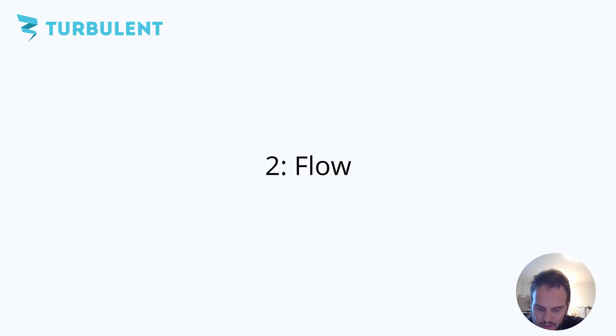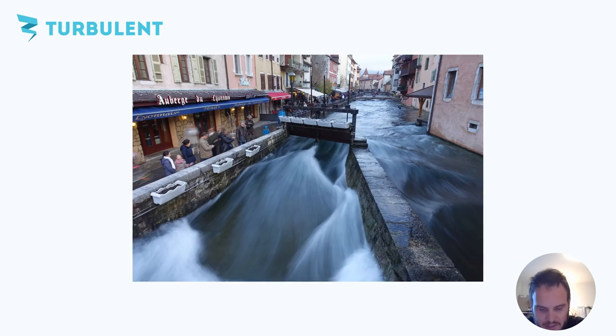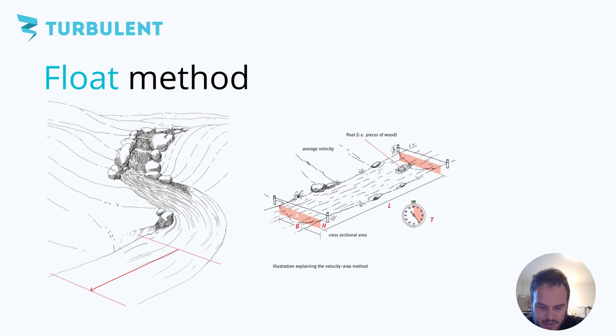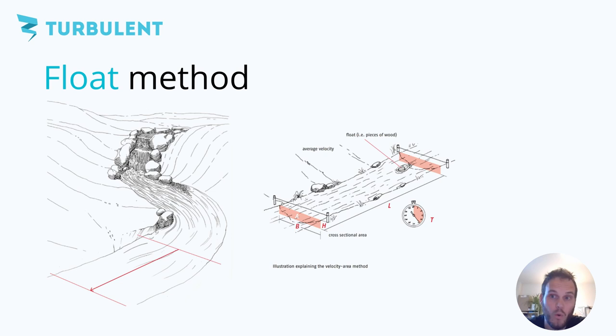Now we can go on to the flow measurement. In low head hydro often times the flows are quite high. This makes them difficult to measure using a standard bucket method or you need to have a very big bucket of course. So what we normally do is the float method. This method is not exactly precise but it's good enough for our purposes. Don't worry about it if we're working here with a few hundreds of liters per second a few liters of measurement error won't have a large impact.